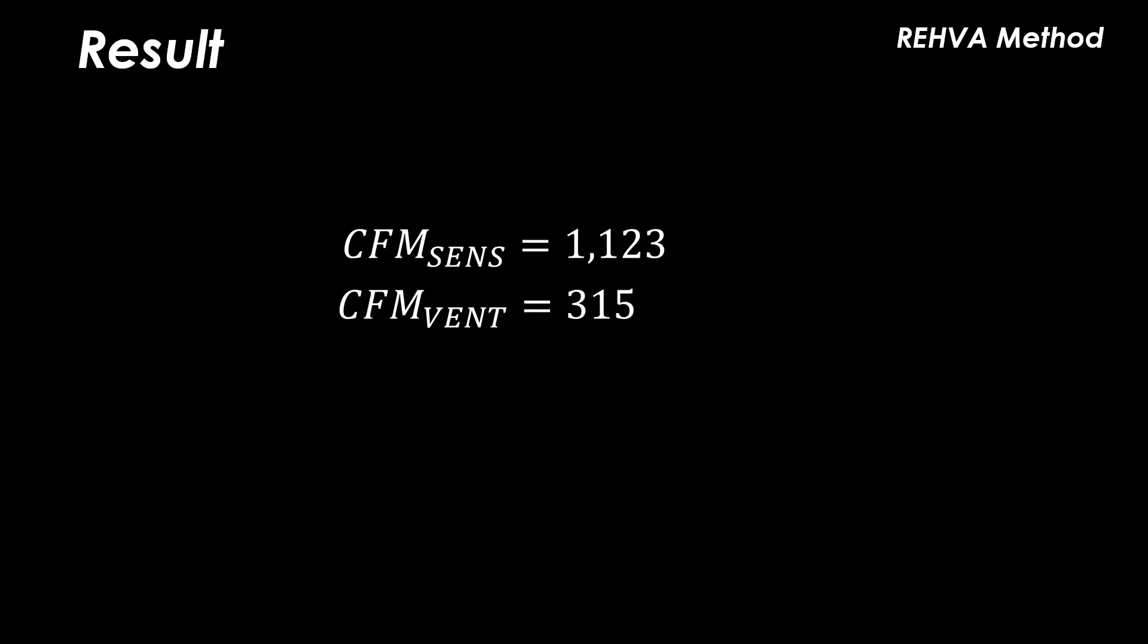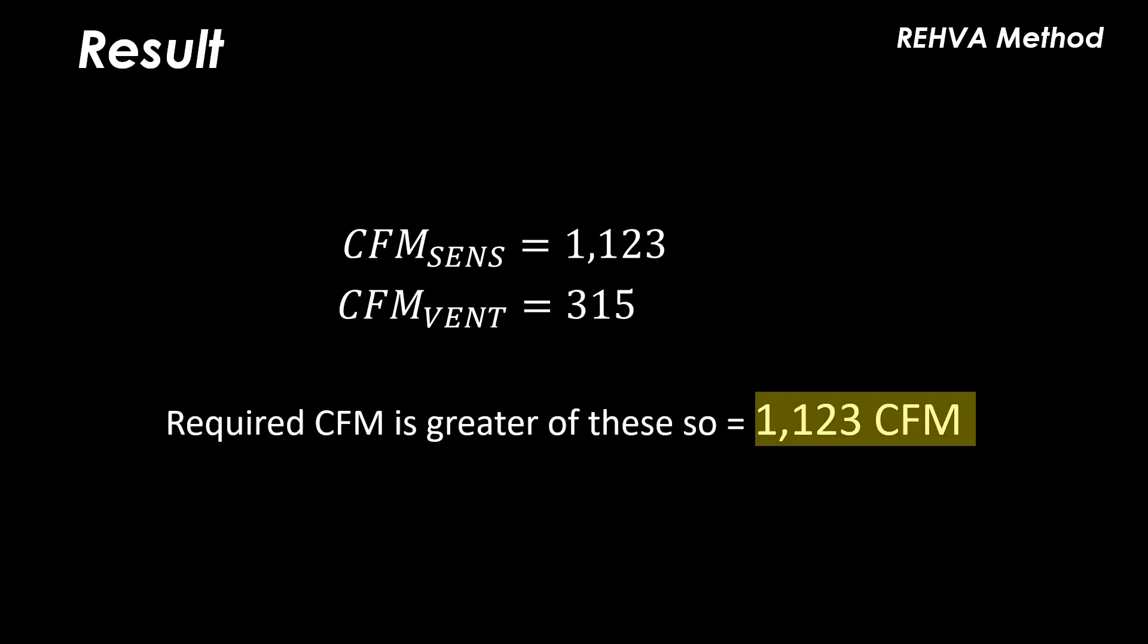Finally, we must check that the airflow required for the sensible cooling is equal to or greater than the airflow required for the ventilation. In part one, we covered the ASHRAE standard 62 calculations for ventilation air, which resulted in 315 CFM for the classroom. The final total CFM required is the greater of the two.